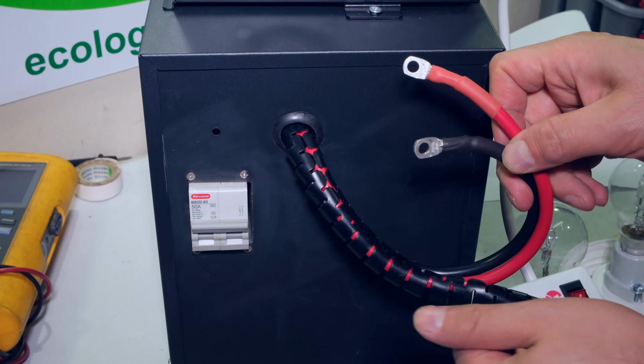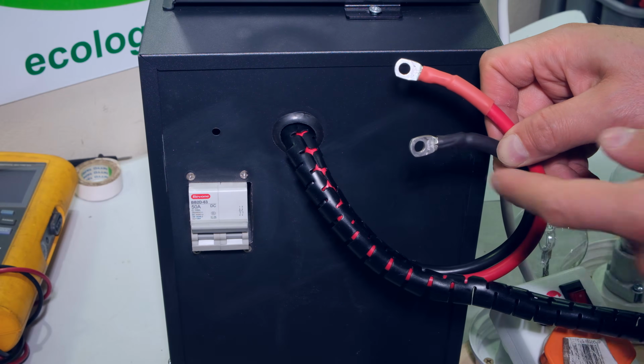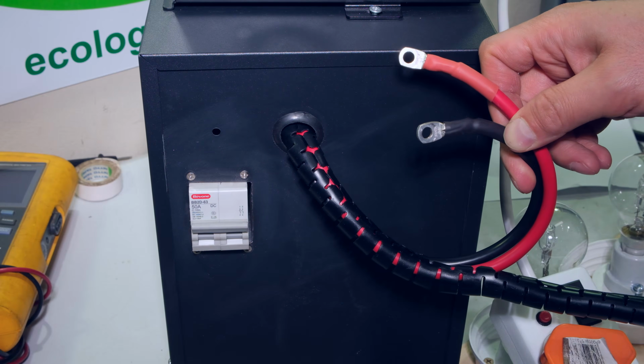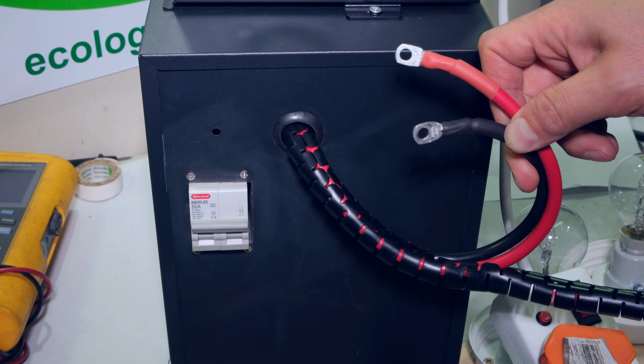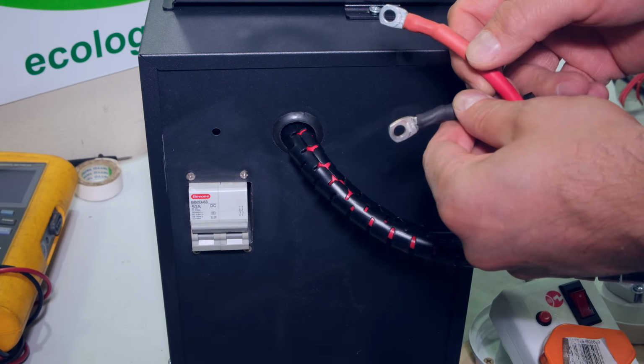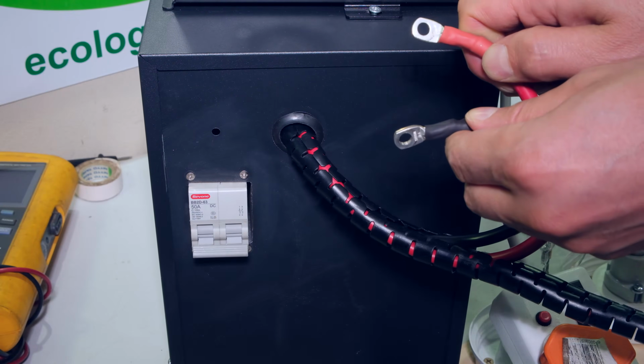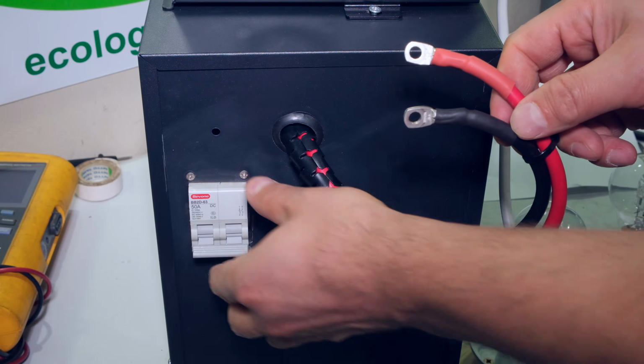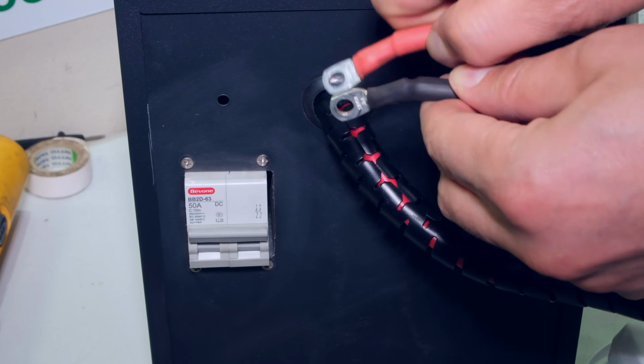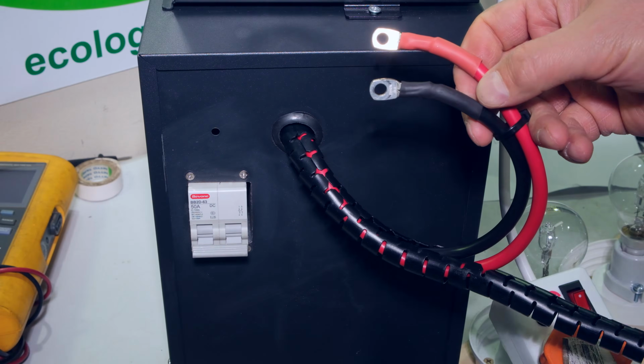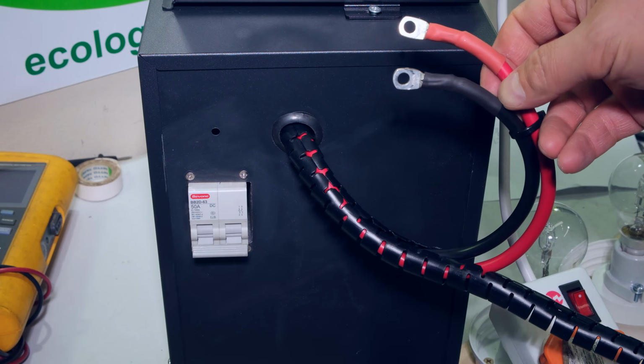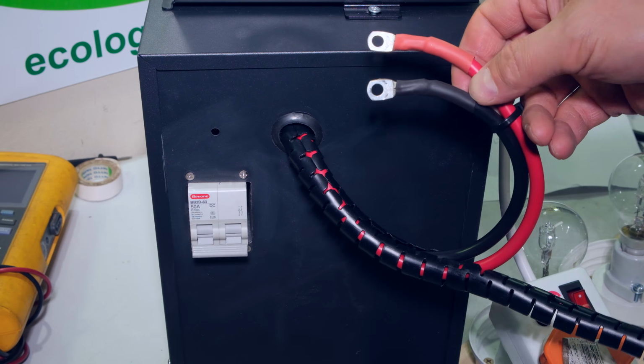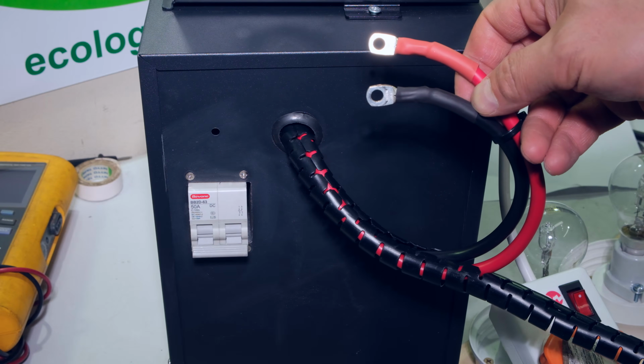Right, I can just test the circuit breaker. There it's in the on position. Here are the terminals. And if I just short them together momentarily, it should trip that circuit breaker. There we go. And test it one more time. Right. So the circuit breaker is working and it is going to protect that battery. And now I can wire this directly into the inverter.